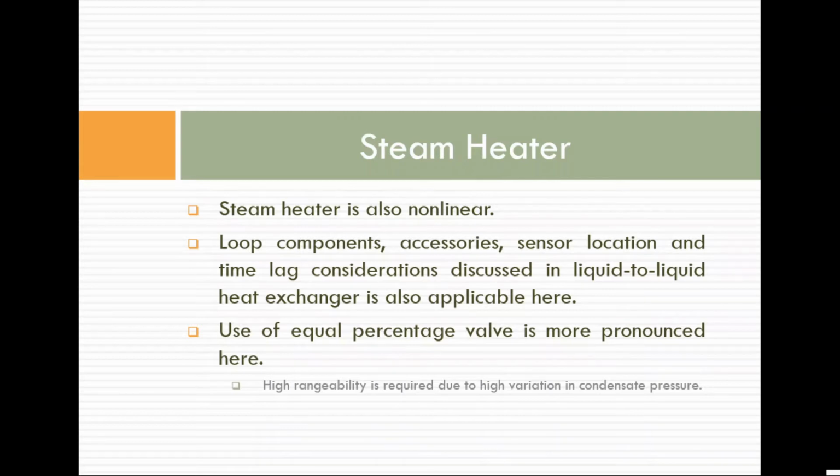If you are considering the measurement location, it must not be far away from the heat exchanger. It must not be very close to the heat exchanger either, so a small adjustment must be there. The second one is time lag. There is some time lag, so we have to consider that also. And we need to use an equal percentage valve.